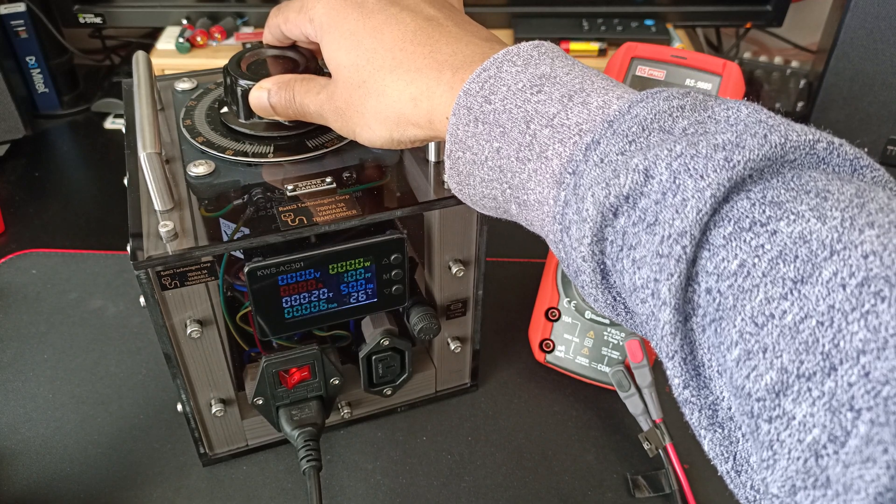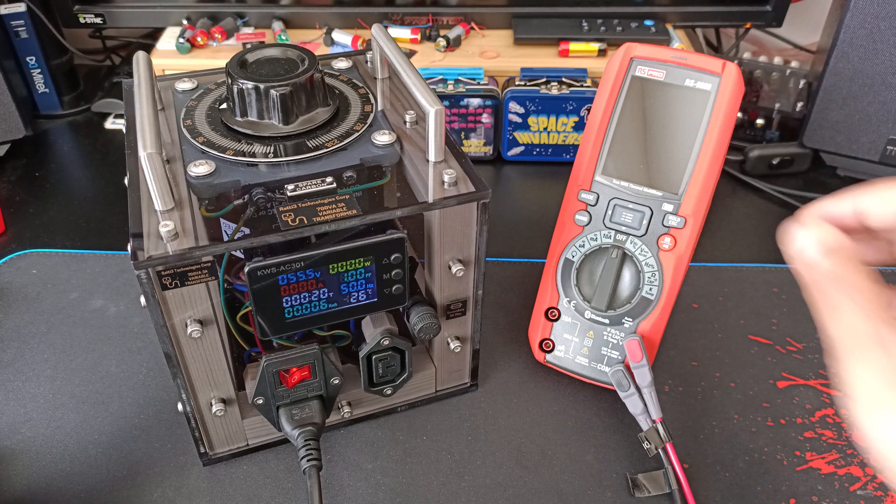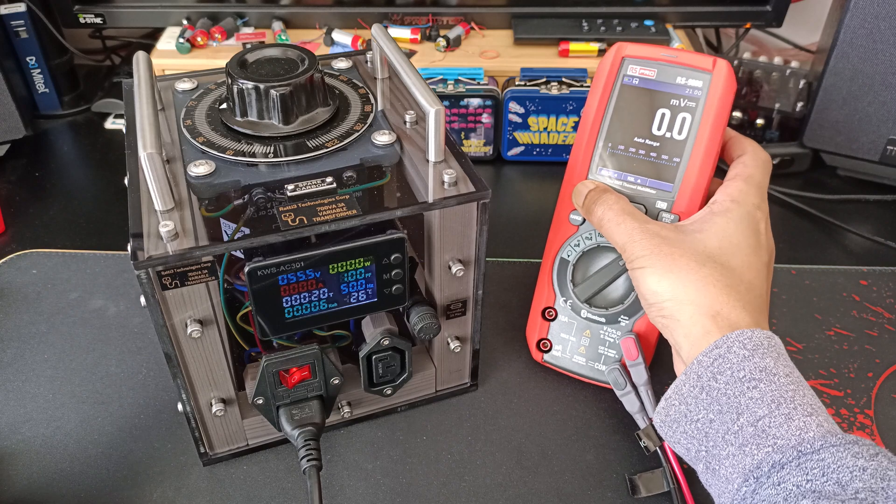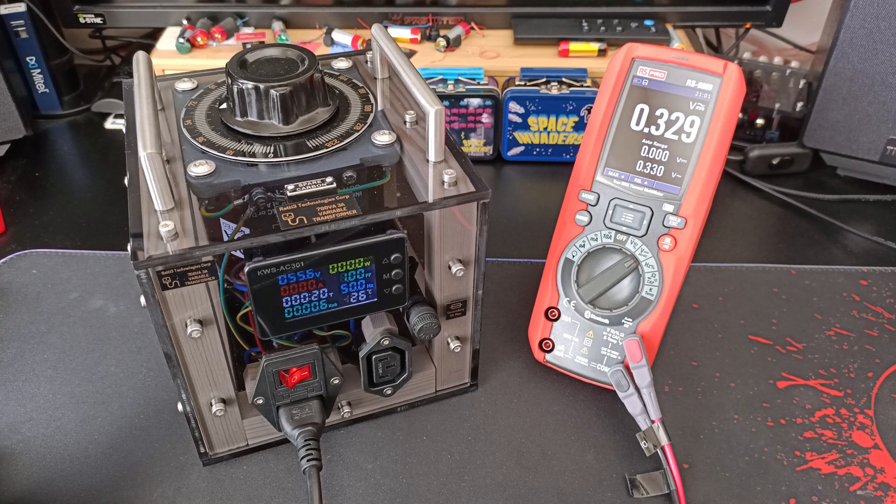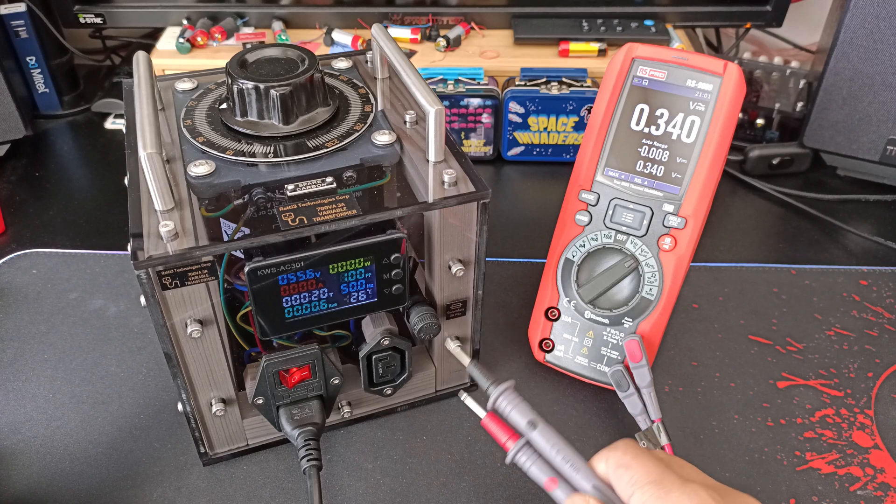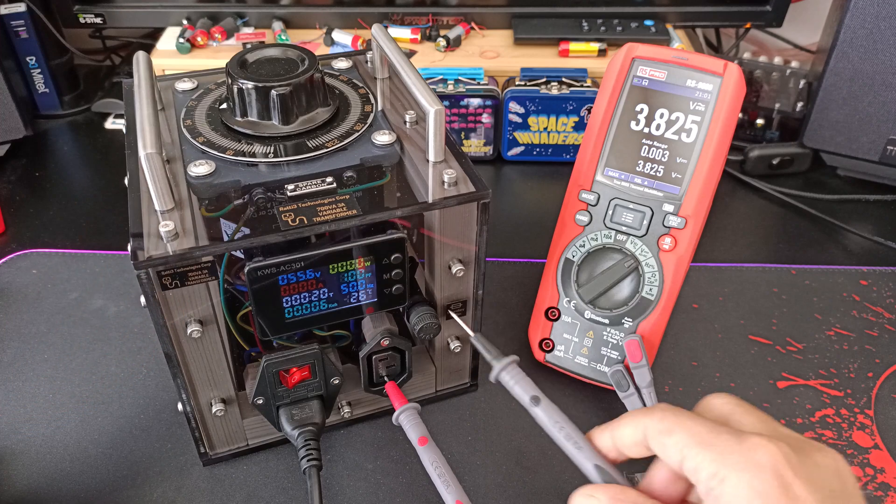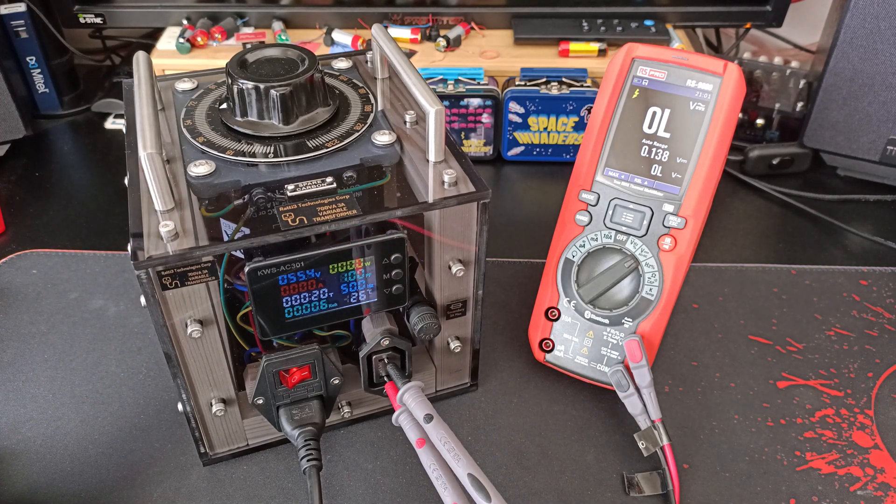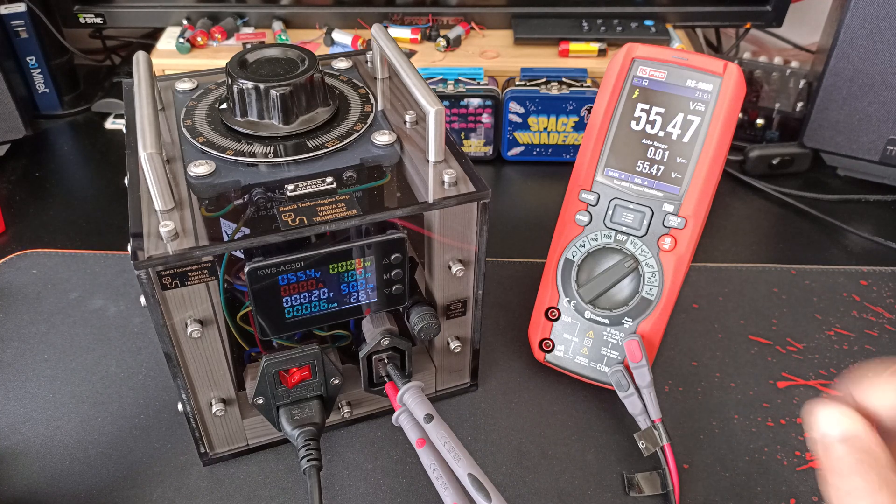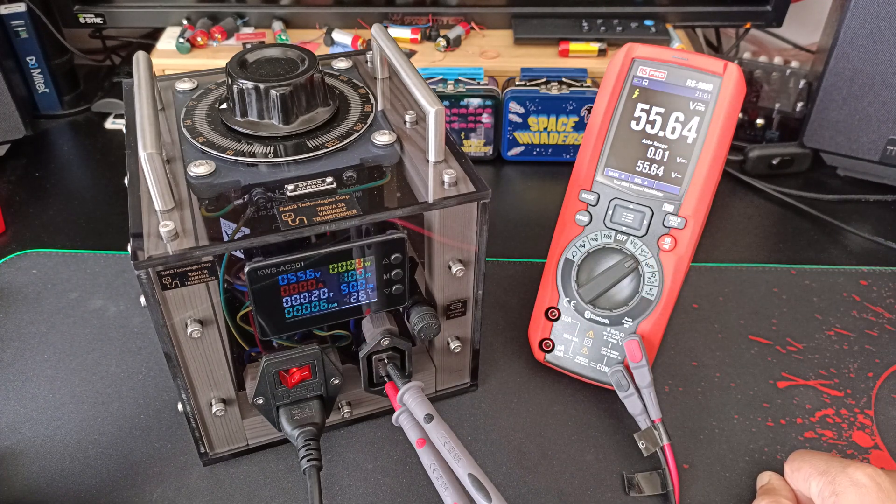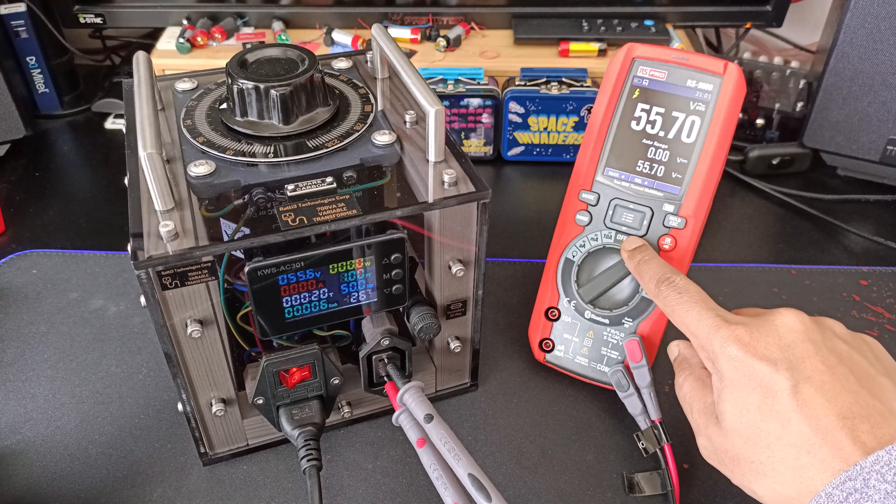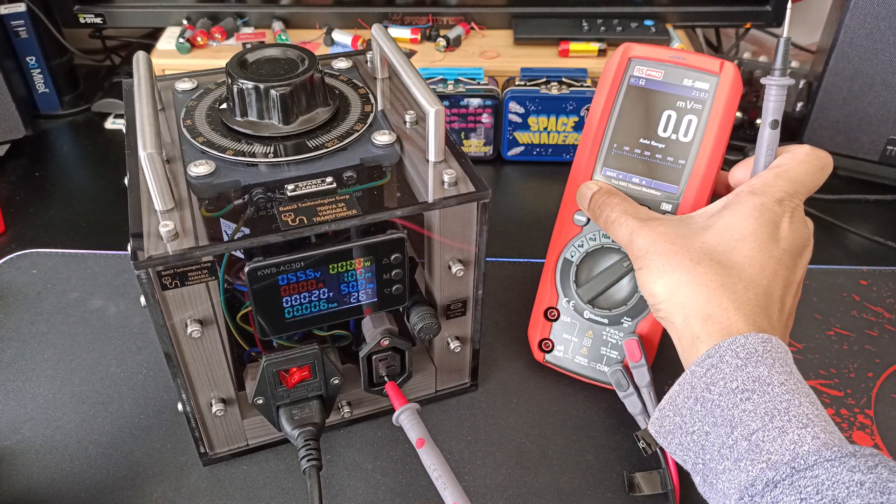The digital meter can only measure from 50 volts. I'll talk about that later. It's on 55.5 volts. Let me turn this multimeter on to AC and start probing. That's pretty accurate. So 55.4 here, 55.55 there. I'll measure the frequency in a second, but it's showing 50 hertz there. It should be 50 hertz.